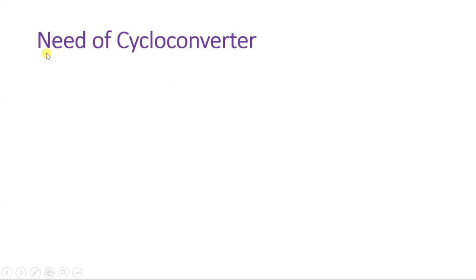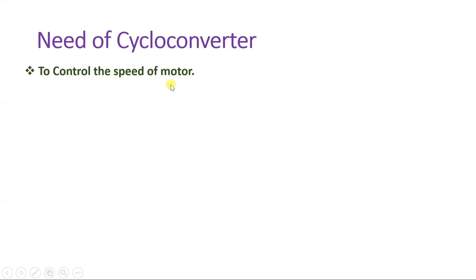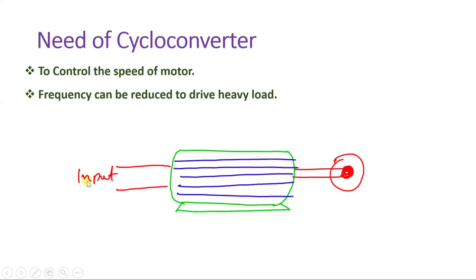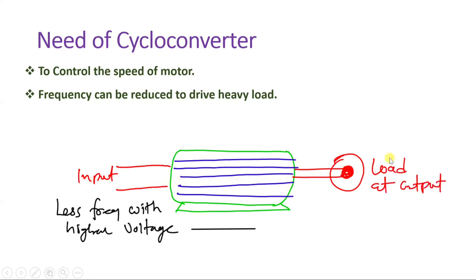A cycloconverter can be used to control the speed of a motor. Different motors have different load handling capacities. By changing frequency, we can control motor speed. If a motor is functioning with a higher load, one way to handle it is to reduce frequency — with less frequency and higher voltage, we can drive a heavy load, since heavy loads cannot be handled at higher frequency.